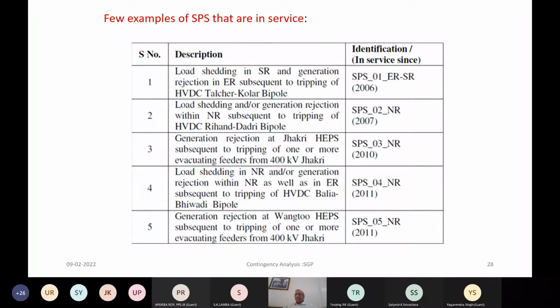There are some examples just for the purpose of illustration. This is one of the papers which was published by NLDC, which had listed out some of the schemes after the implementation. For example, the first scheme which I mentioned is load shedding in southern region and generation rejection in eastern region, subsequent to tripping of the HVDC Talcher Kolar bipole. This HVDC line, if it trips, then there is a load rejection in southern region and generation rejection in eastern region. So this is one example where the power system element is an HVDC line between Talcher and Kolar, but the actions are taken in the southern region and eastern region, which are totally away from the element which is under fault.